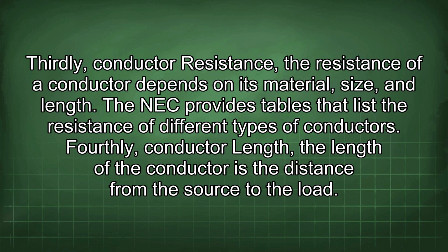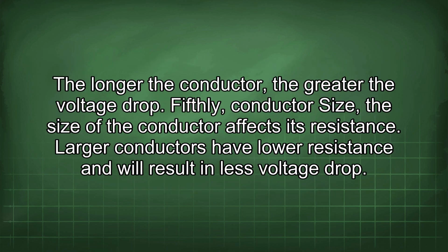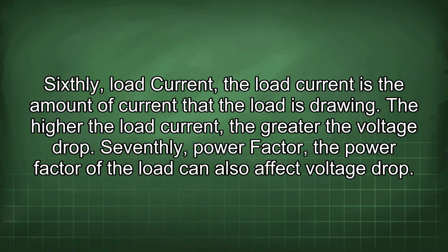Fourthly, conductor length. The length of the conductor is the distance from the source to the load. The longer the conductor, the greater the voltage drop. Fifthly, conductor size. The size of the conductor affects its resistance. Larger conductors have lower resistance and will result in less voltage drop. Sixthly, load current. The load current is the amount of current that the load is drawing. The higher the load current, the greater the voltage drop.